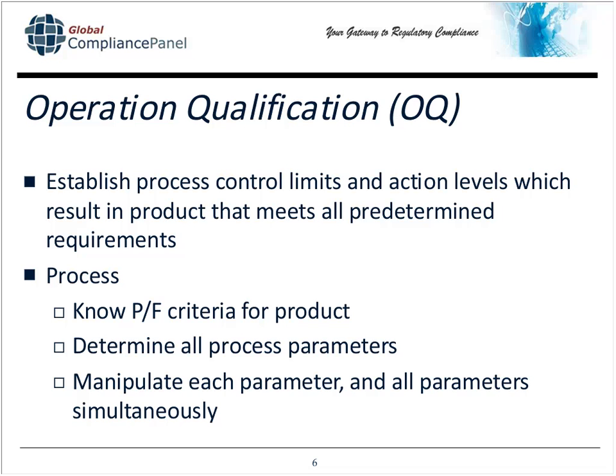You also want to determine your process parameters. I've been using temperature exclusively throughout the discussion to this point, because there are other process parameters that deal with a sealing machine. There's dwell time, which is the amount of time the pouch travels through those jaws that provide the heat. And there's pressure. There's an amount of pressure that the pouch has to be subject to.